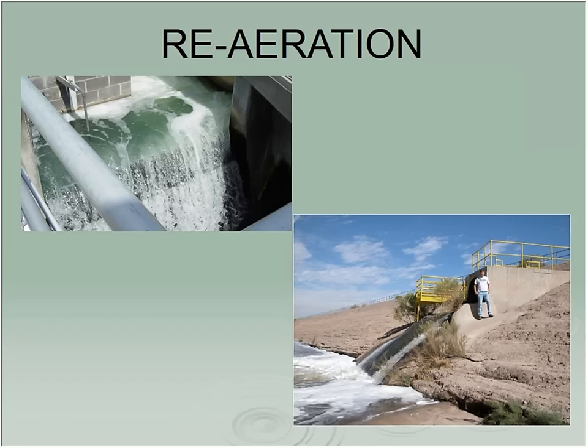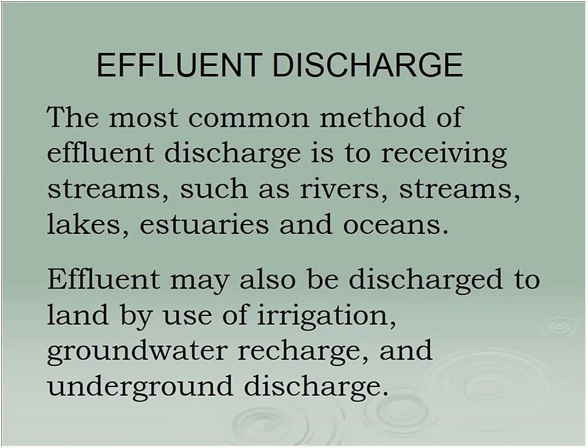Upper Blackstone, again, is very fortunate, and their water all flows downhill. When it comes out of their contact chamber, it goes over a weir similar to this and then drops about 8 feet. Got 6 in a heartbeat by doing that. Some other places, you go to Brockton, it cascades somewhat similar to this down a series of steps. All that, just that little bit of activity is enough to get that oxygen to it for free. So now when it goes in, it doesn't kill off the oxygen in the stream. It just kind of blends right in and hopefully you never see anything.